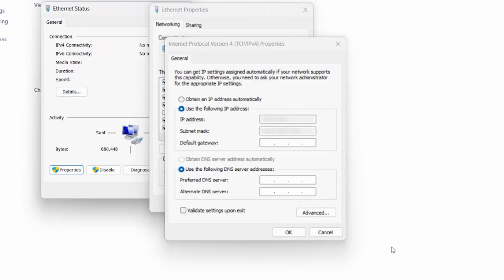Okay, so now let's take a little bit of time and be sure we get communication going from our Axos system to our computer. The first thing we're going to need to do is make some adjustments in our Internet Protocol version 4 properties, which you can see we have pulled up right here. And this is how it looks on the Windows system.